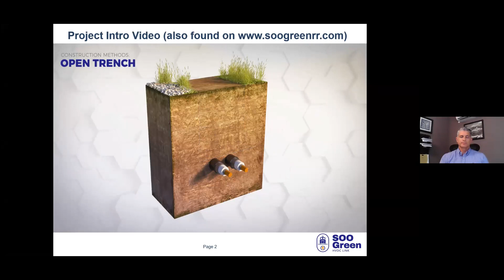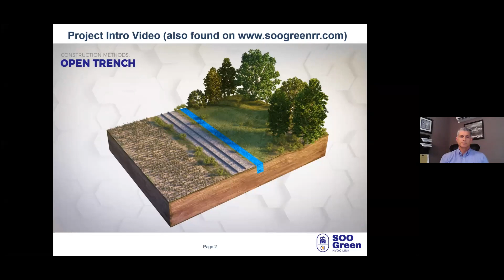During open trenching, SOO Green will dig an approximately 3-foot wide, 5-foot deep trench and bury 2 8-inch diameter conduits. The trench will be backfilled, creating a duct bank with a minimum 3-foot ground-level clearance. Once the duct banks are in place, native soil will be replaced and restored. Cross-linked polyethylene insulated cables, each about 5 inches in diameter, will then be pulled through the conduits. These installations require no coolant fluid. Once in place, the trench will remain closed for the life of the project.